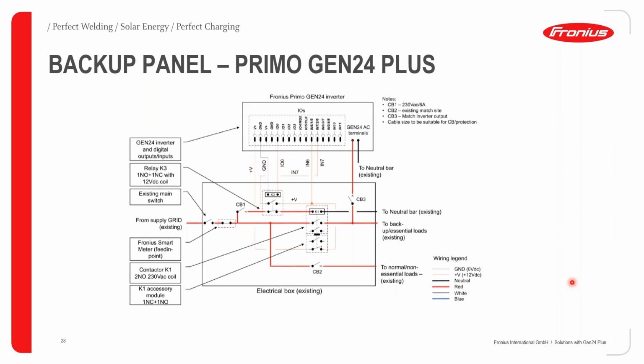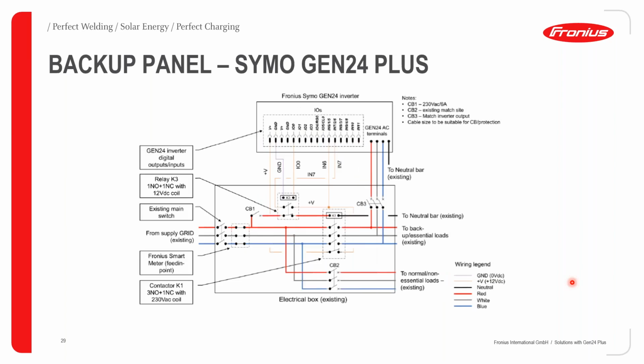So this will be your setup for the Gen24 Plus. Then having a look at the setup for the Symo Gen24 Plus, because now we're dealing with 3 phases, you now need a few additional components in the backup box. Having a look at relay K3, we will now have a normally open, normally closed relay, which will be supplied with 12 volt DC from the pilot card.